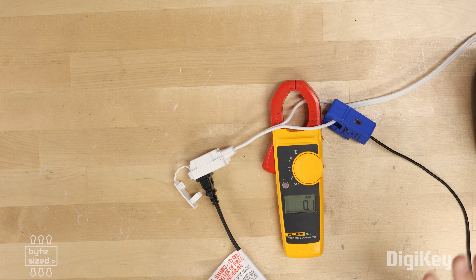The space heater is currently off, so it's not pulling any current. The Fluke meter is reading 0.1 amps. Now I'm going to open up the Home Assistant app on my phone to read our current transformer. It's currently reading 0.14 amps. But let's turn on the space heater and see what happens.